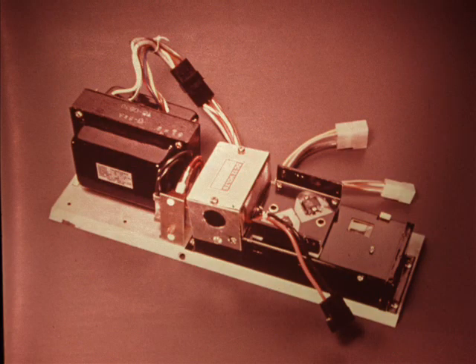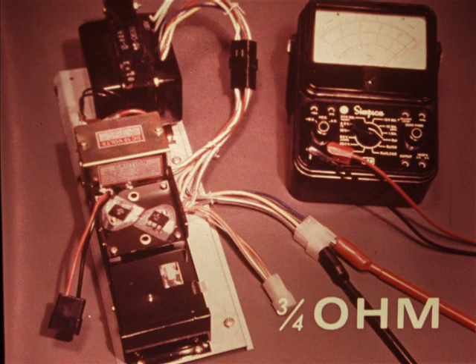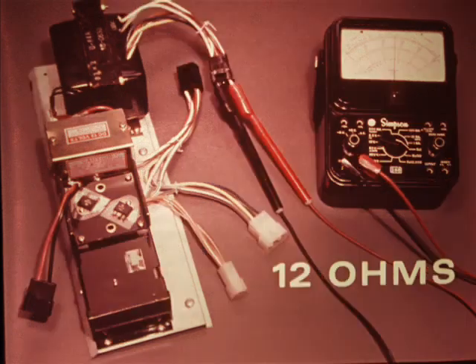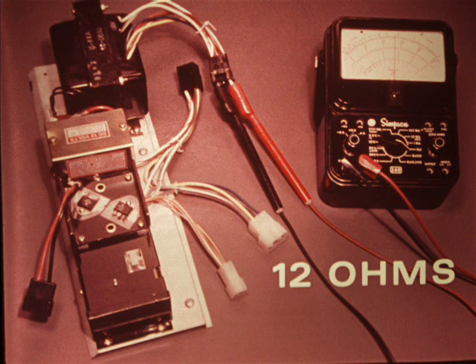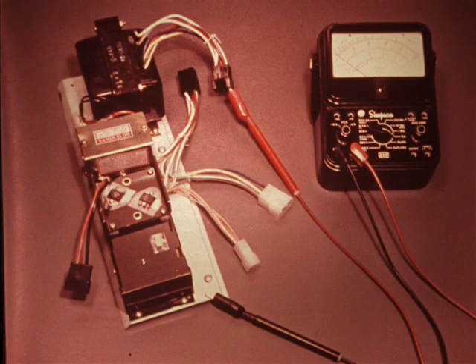The transformer should be tested first, both the primary and secondary windings. We're showing the test on the bench for convenience, but it can be done on the vehicle. Test the secondary windings at the blue and yellow transformer leads of the thermostat connector. There should be continuity through the windings with a very slight resistance, perhaps 3/4 of an ohm. Test the primary windings by opening the inverter to transformer connector and measuring resistance between the white and white-green wires. The winding resistance should be about 12 ohms. Also, touch one of the ohmmeter leads to the mounting plate to test for grounding. There should be no continuity.